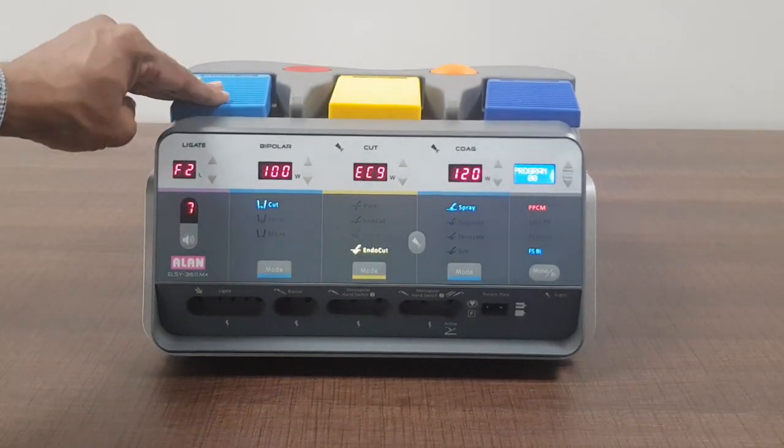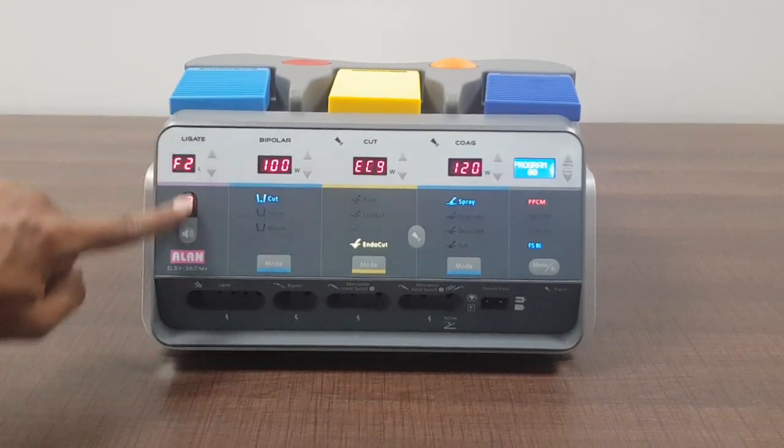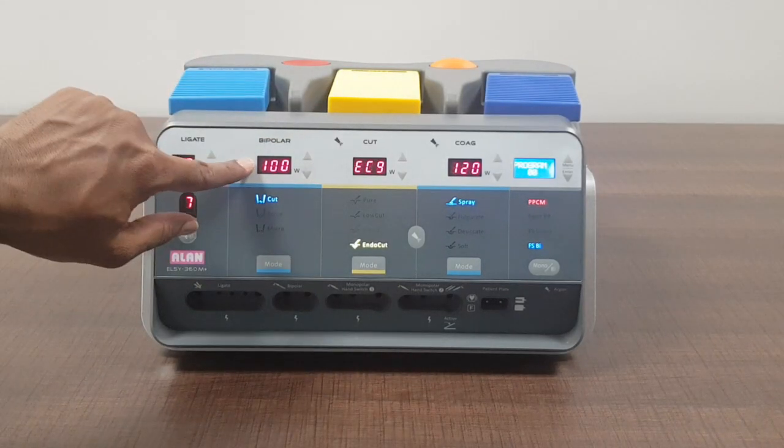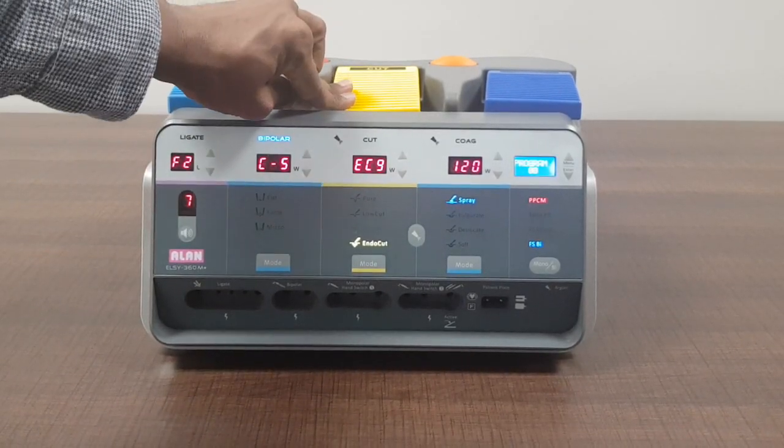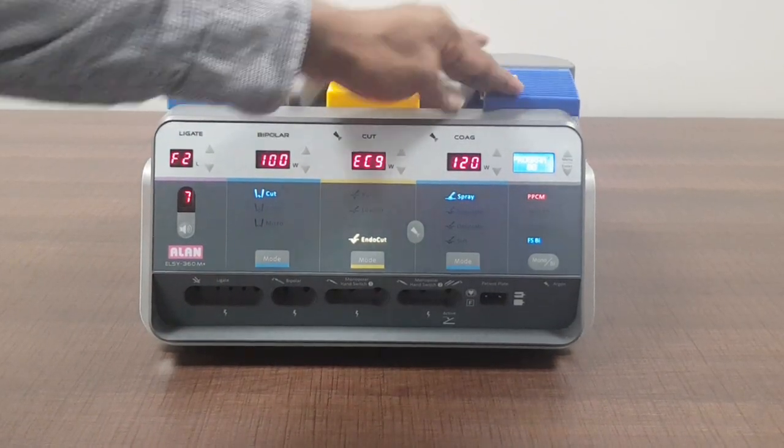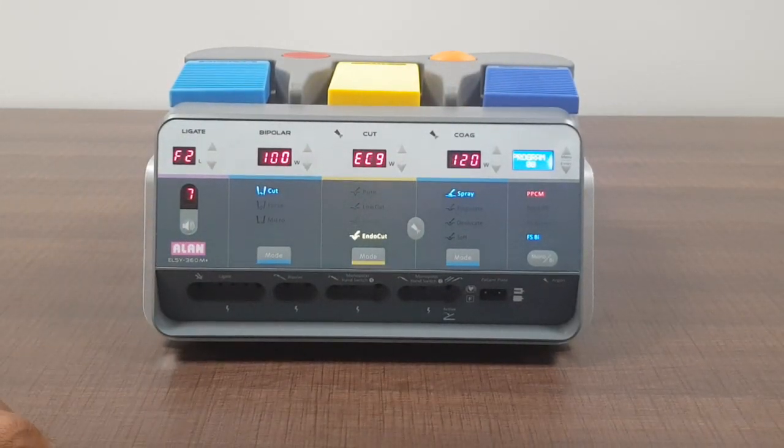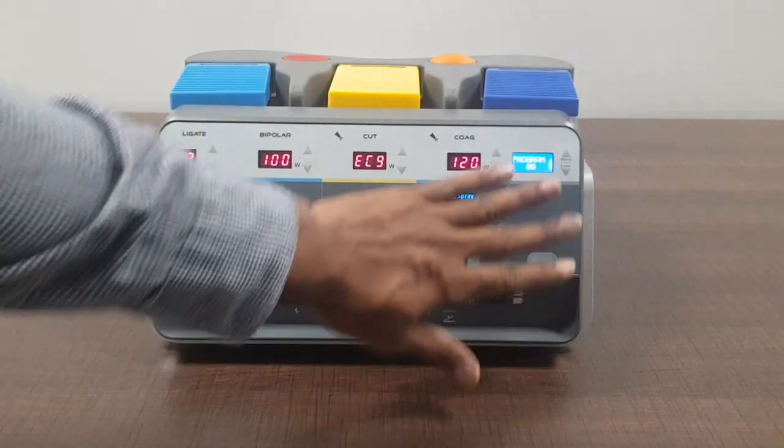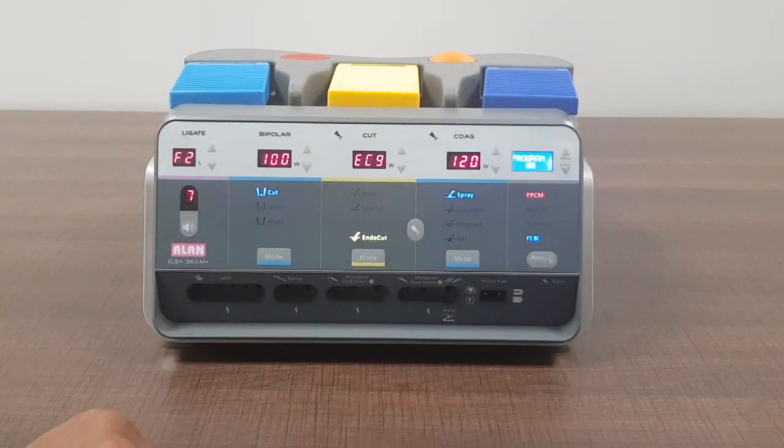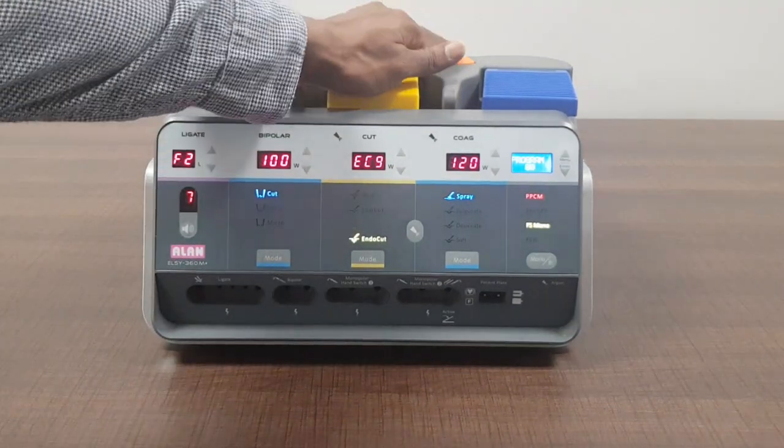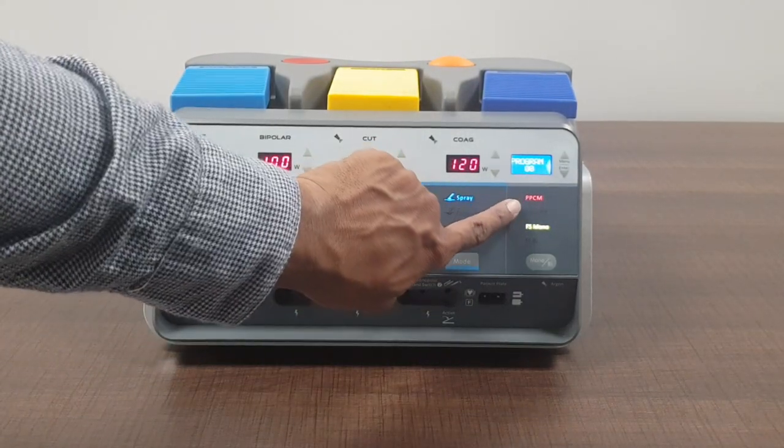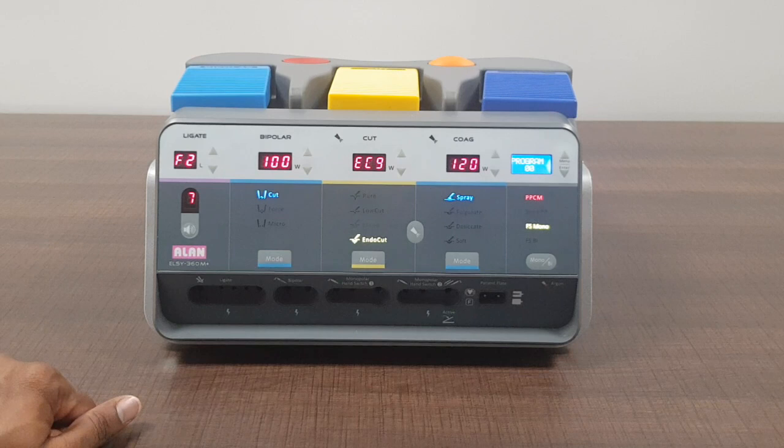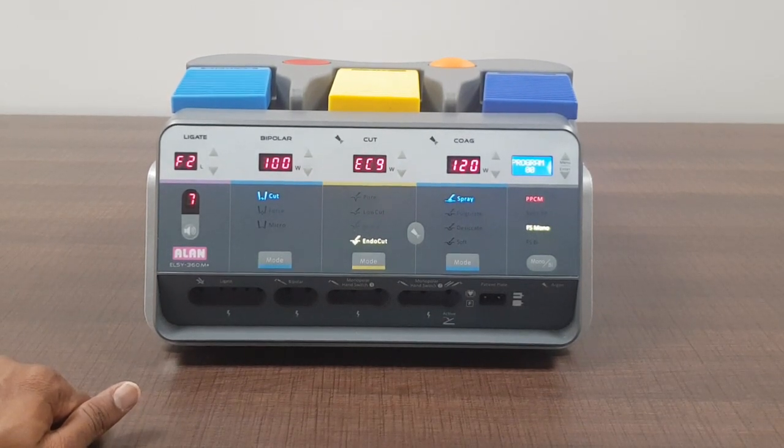If I press this one it has gone to bi which means now, this will just focus here, see, this pedal will work for, like this pedal will work for, if I press it you will get C5, see this. This is for cutting but using bipolar and this is for bipolar coagulation. So this way you can switch the foot pedal and the best part is you don't have to go to the screen and press it to keep switching the mode. Just using the foot pedal with your leg press it, it can tell you. And also if you see the PPCM here it will show you whether you are using a split type of patient plate or a normal patient plate.